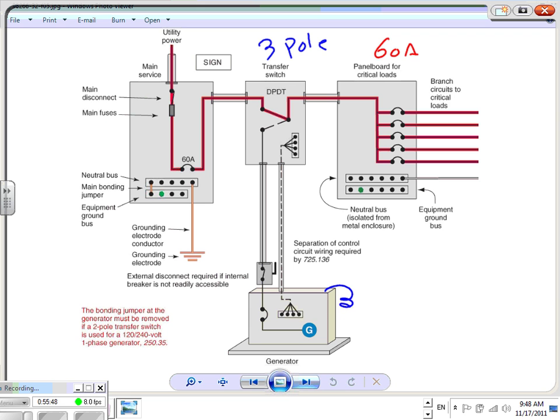If you look inside the generator, you have the hots. Here's my hot coming in here, and here's my other hot coming in here. Let's go to the neutral, using green. Right inside the generator, which is like the transformer, I bring my neutral directly to the ground, and I switch my neutral. So I grounded the neutral right at the generator, and I went into a grounding electrode conductor that I'm driving right next to the generator, or tying into the existing grounding electrode rod in the area.